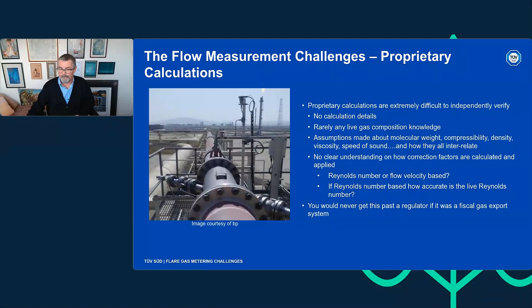So, the flow measurement challenges in summary: low flows are challenging, installation effects are challenging, proprietary calculations are challenging, and another subject given a lot of consideration recently: are we doing routine maintenance that potentially makes things worse? We do routine maintenance on flare meters, which generally involves removing the transducers. Transducers can be quite substantial in length, and we put them back in. Are we absolutely sure we've put them in exactly the same place, and that the geometry is exactly as before? Perhaps it is, but perhaps there are other ways to maintain ultrasonic meters, for example condition-based maintenance. If we know the speed of sound and the signal strength, there may be ways to know that maintenance isn't needed at that particular time.